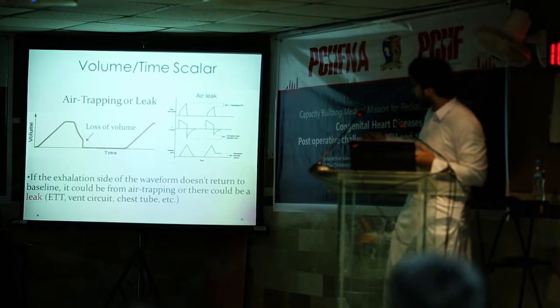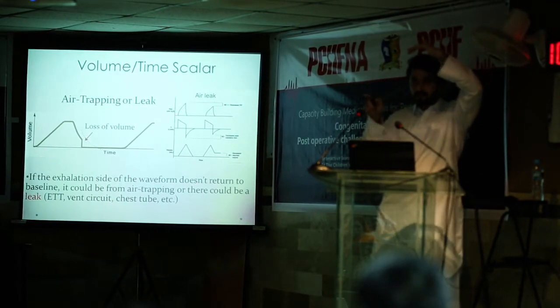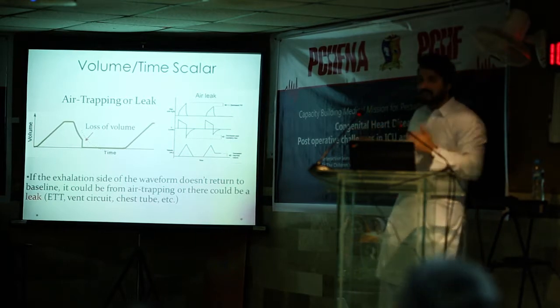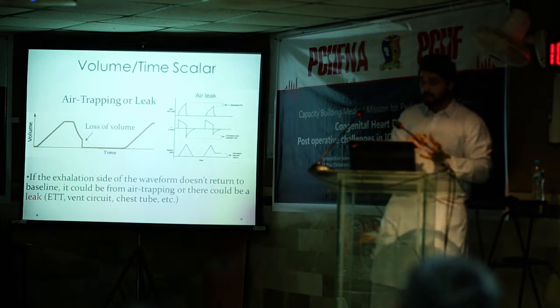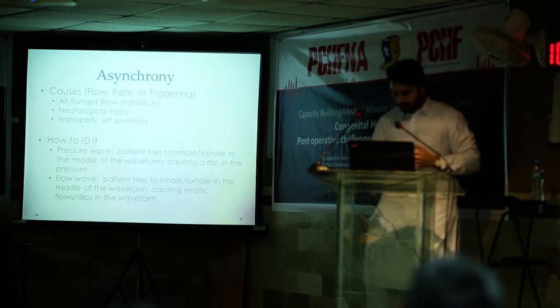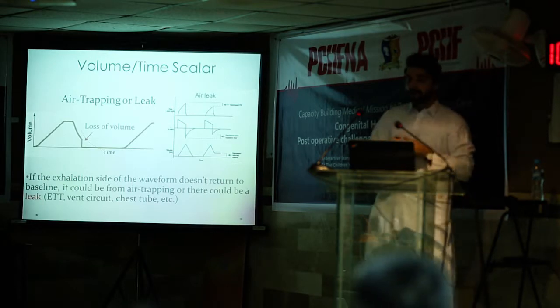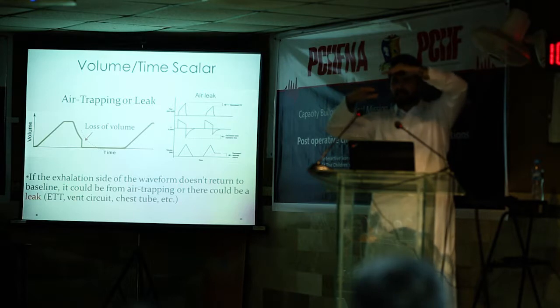By the pressure. In air trapping, the pressure will be high, especially the PIP, because of the resistance. But in a leak, the pressure will be low, because there is a leak.